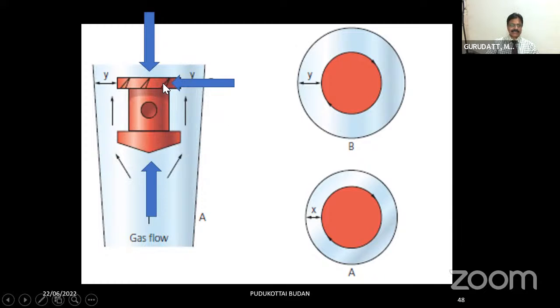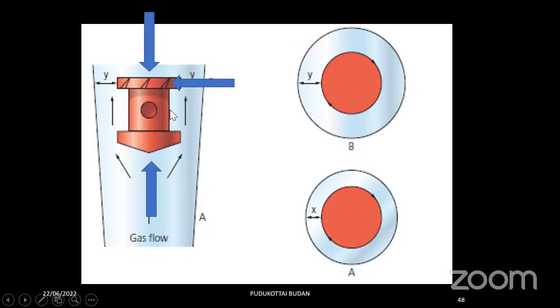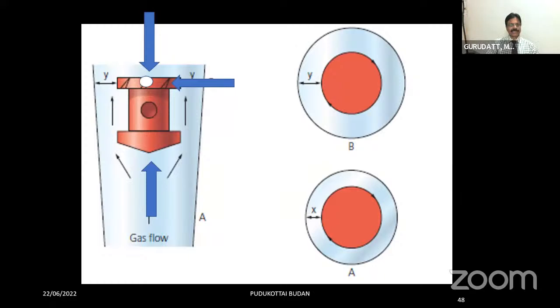The other thing you can see here is that there are flutes on the upper margin of the bobbin. These flutes are deliberately made, because when the gas starts flowing, it is going to hit these flutes and then rotate the bobbin. So the rotation of the bobbin is very important. This rotation can be seen because of a fluorescent dot that is always present at the upper margin of the bobbin. Even in dark rooms, you can see this fluorescent dot, especially in radiology suites when you're using the anesthesia workstation. Also, the back of the flow meters has a fluorescent backing, so that you can continuously visualize the bobbin rotating. Now with modern workstations, we have lights in the flow meter assembly, so you can just put on the lights and you'll be able to see the rotation of the bobbin.